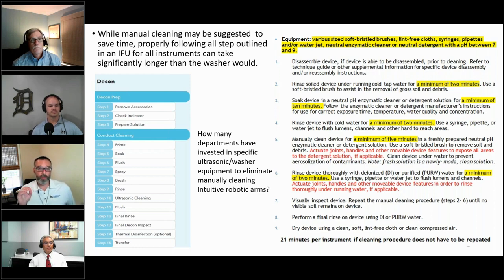And then, by the way, this would be per instrument: 2 minutes of rinsing, a minimum of 10 minutes soaking, a minimum of 2 minutes rinsing, manually cleaning for 5 minutes, a minimum of 2 minutes with another rinse, visual inspection. When you add this up, 21 minutes per instrument. So if anybody ever says, go ahead real quick and hand wash this for me, you can get the whole set through your washer in 21 minutes, as opposed to standing there washing each one for 21 minutes, right?